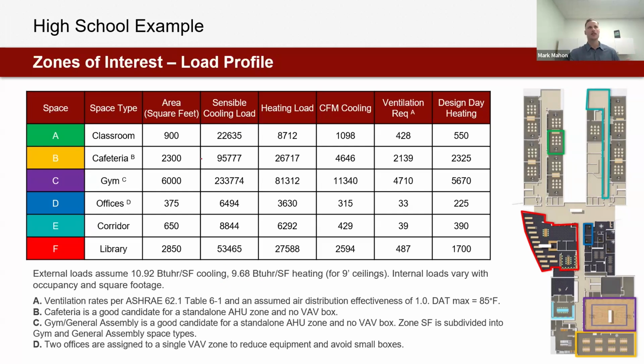What I have for each of these zones is their square footage, their sensible cooling load requirement, which is based off of an external load of 10.92 BTUs per hour per square foot for cooling, the heating load, which is based off 9.68 BTUs per square foot for heating, and then I did full internal loads based off of occupancy, square footage, electrical distribution, all that kind of stuff.